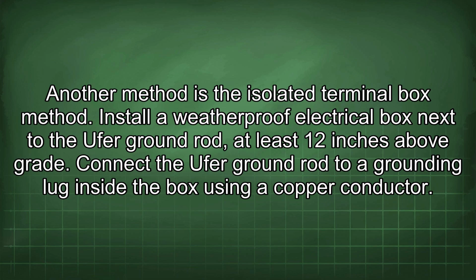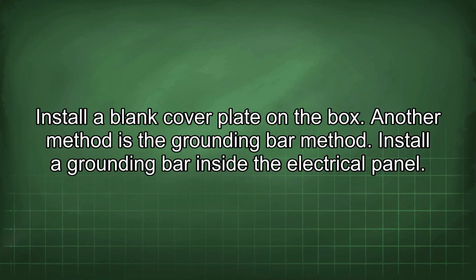Another method is the isolated terminal box method. Install a weatherproof electrical box next to the Ufer ground rod, at least 12 inches above grade. Connect the Ufer ground rod to a grounding lug inside the box using a copper conductor. Install a blank cover plate on the box.